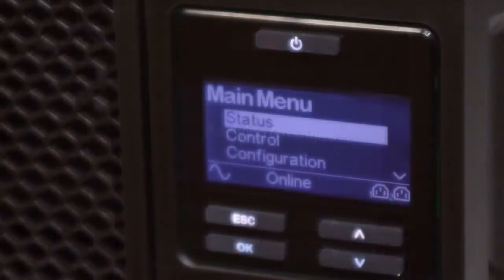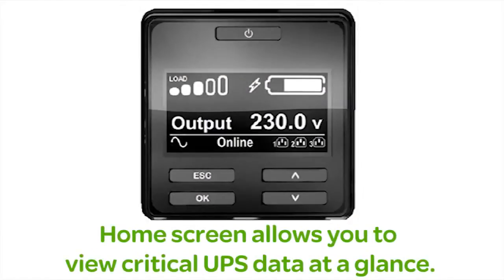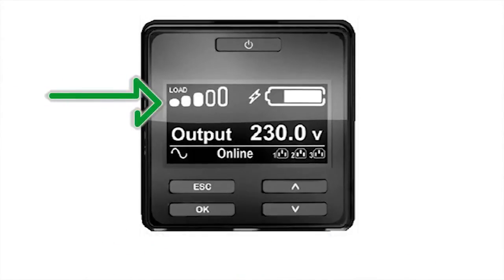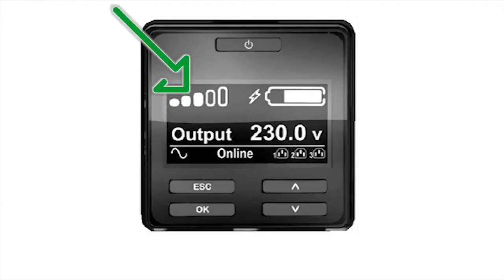Users can change any of the selected options once they've exited the setup wizard. The LCD status screen displays a wealth of valuable information. The load indicator displays present UPS load in relation to overall UPS capacity. The approximate load capacity percentage is indicated by the number of load bar sections illuminated, with each bar representing 20% of the load capacity.